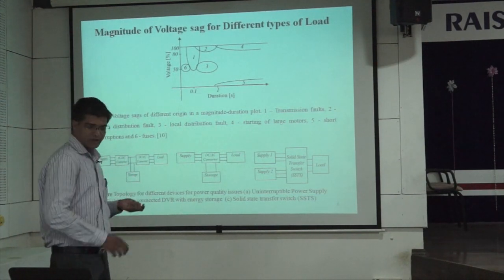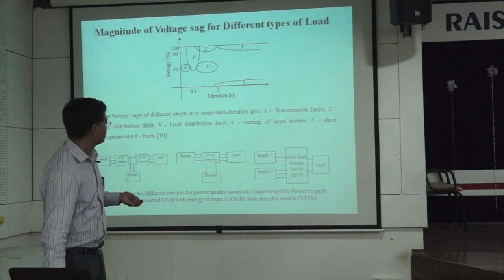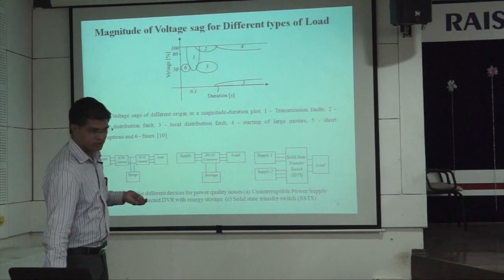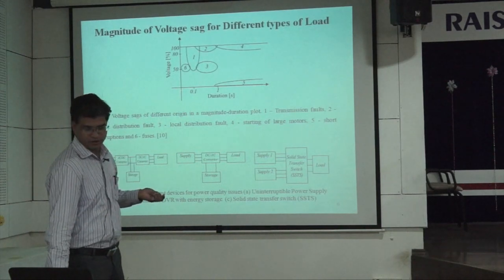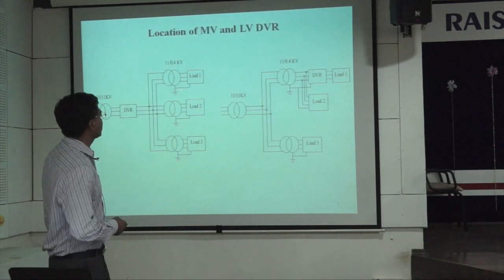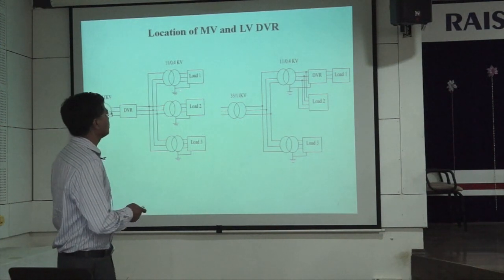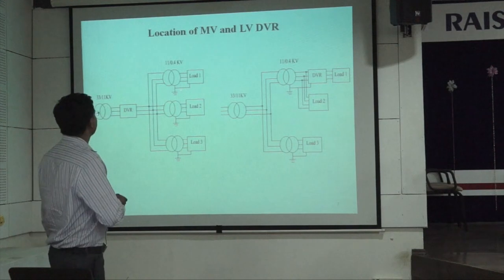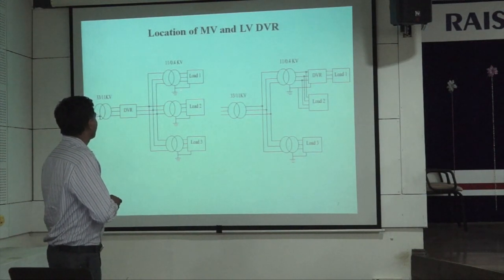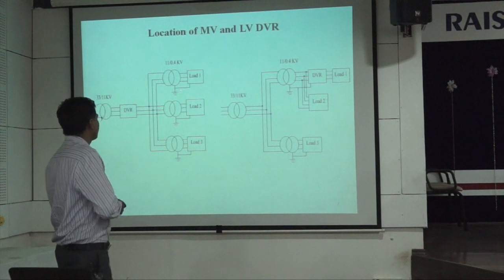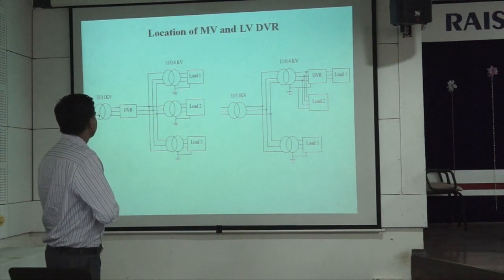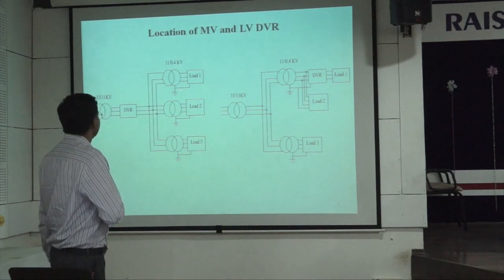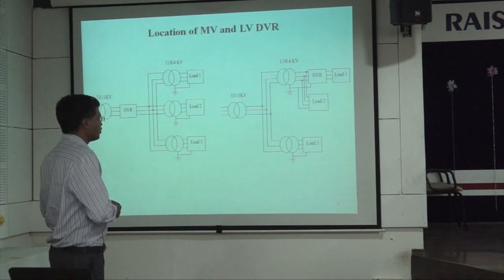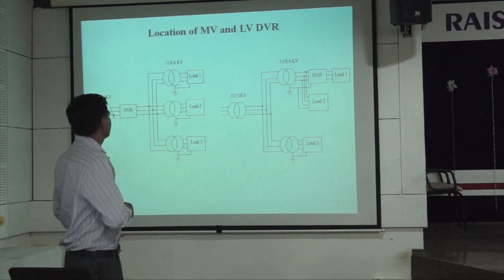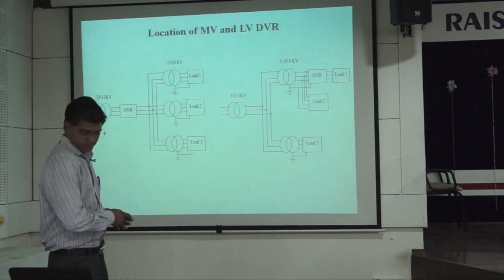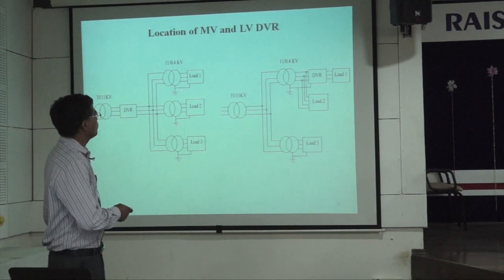That's why I have concentrated on the DVR, because I can minimize the rating of the DVR and it will be a more cost-effective solution for the power quality problem related to voltage. Now there are various locations where we can connect the DVR. It can be at the medium voltage level or at the low voltage level. For power quality improvement, different types of load can be connected at the distribution end, but the rating of the DVR connected at the medium voltage will be much higher, and we require more energy storage as compared to the low voltage DVR. So that's why I have concentrated on the low voltage DVR first.